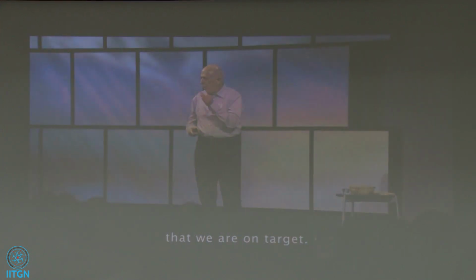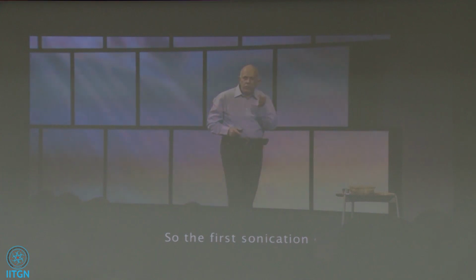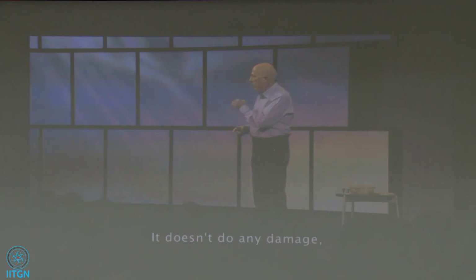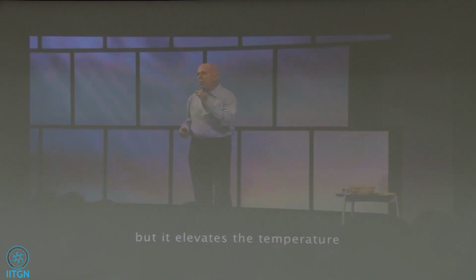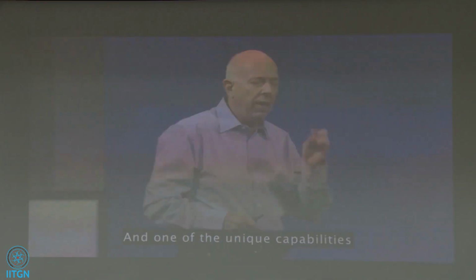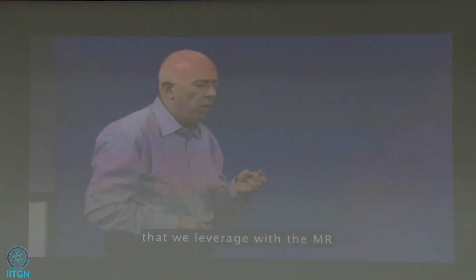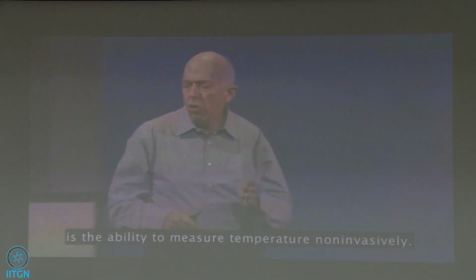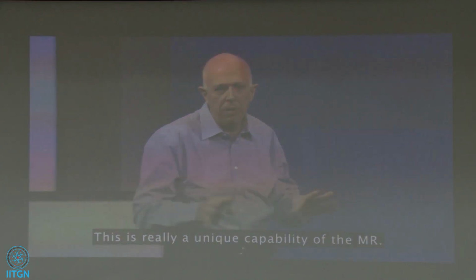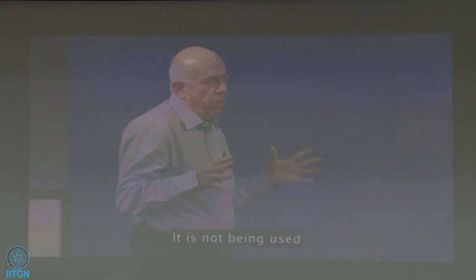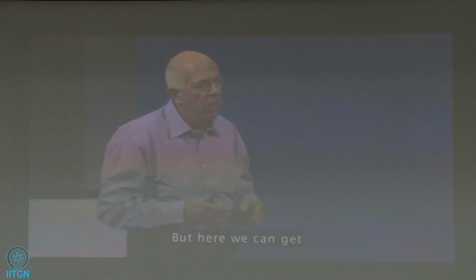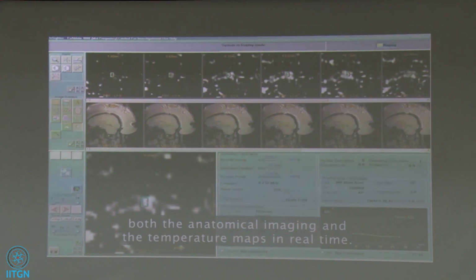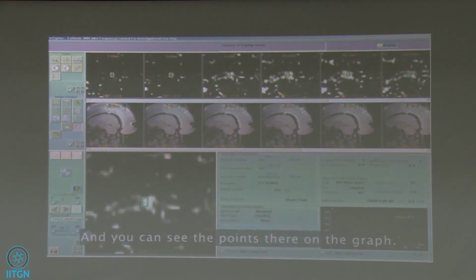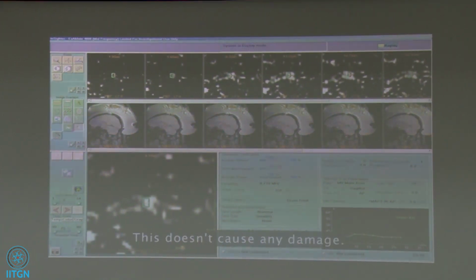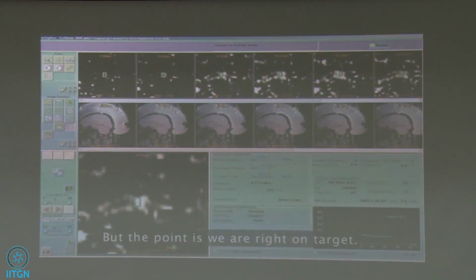We first need to verify that we are on target, right? So the first sonication is at low energy. It doesn't do any damage, but it elevates the temperature by a few degrees. And one of the unique capabilities that we leverage with the MR is the ability to measure temperature non-invasively. Okay, this is really a unique capability of the MR. It's not being used in regular diagnostic imaging. But here, you can get both the anatomical imaging and the temperature maps in real time. And you can see the points there on the graph. The temperature was raised to 43 degrees temporarily. This doesn't cause any damage. But the point is, we are right on target.